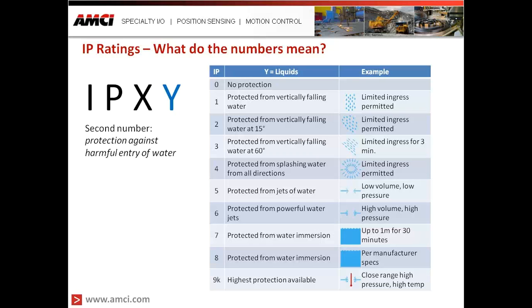Just like with the solids, the numbers start at zero and increase all the way to 9K. Looking at the chart, protection levels one through three cover limited entrance or no entrance of liquids, whether that liquid is falling vertically or at a particular angle — a practical example here would be rain or blown rain. When we look at an IP rating of four, we see protection from splashing water from all directions. A practical example would be something like a ship near shore with waves splashing, water crashing, or maybe a keyboard with coffee spilled on it — you want protection from splashing liquids.